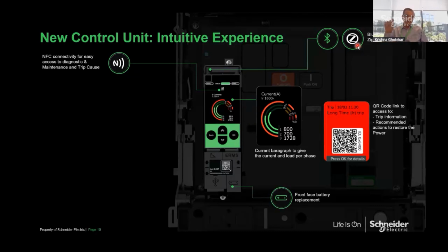Now there are indication LEDs on the breaker. You have seen them, for the overload, short circuit, for the different faults. Then there is a pre-alarm and so on. Now to power up these LEDs, there is a battery in the trip unit. As of today, the battery is on the backside of the breaker. So let's say after 10-15 years, if the battery dries down, to replace it you have to remove the trip unit and then install the battery. The battery powers the LEDs, not the display, because the display takes its power from the main supply, or if you have given 24-volt DC. For the LEDs, if the battery is dried down, you get a warning message on the display, and to change the battery, it's from the front flap of the trip unit.